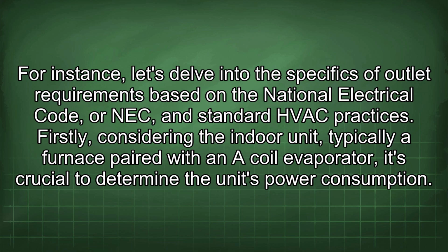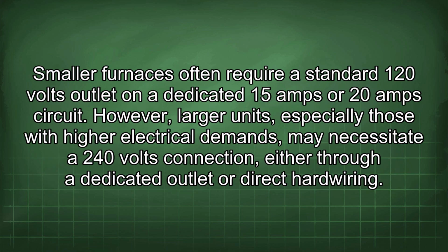For instance, let's delve into the specifics of outlet requirements based on the National Electrical Code, or NEC, and standard HVAC practices. Firstly, considering the indoor unit, typically a furnace paired with an evaporator coil, it is crucial to determine the unit's power consumption. Smaller furnaces often require a standard 120 volt outlet on a dedicated 15 amp or 20 amp circuit.